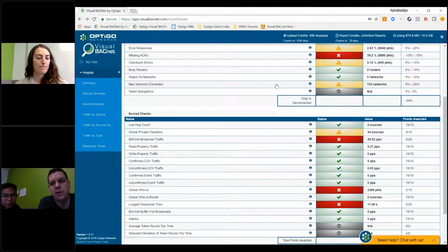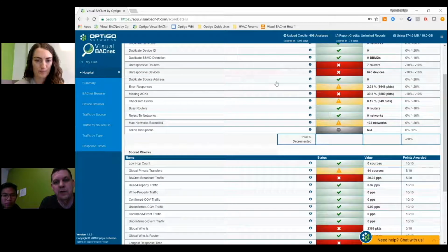Most systems could handle 100 or 150 networks. Some can handle up to 400 or 600 networks. It's always an idea to ask, how many am I handling, and can my existing router hardware handle it? If you just add another couple of buildings and haven't changed any of that infrastructure, this will trip, and then you could go back into our unresponsive router problem, because you've just put a big load on it that it can't actually take.